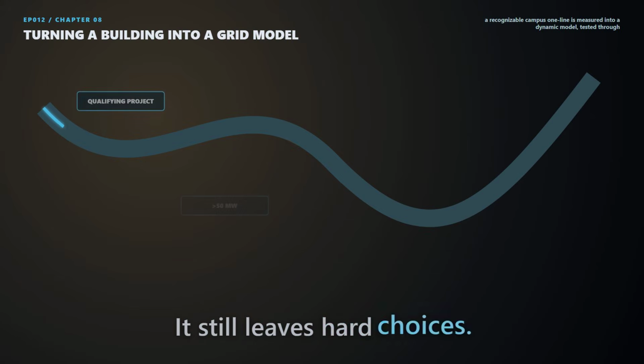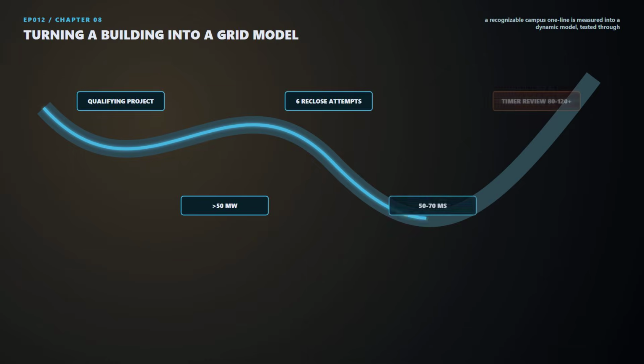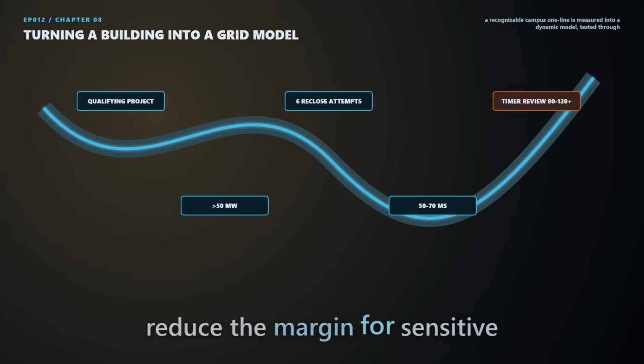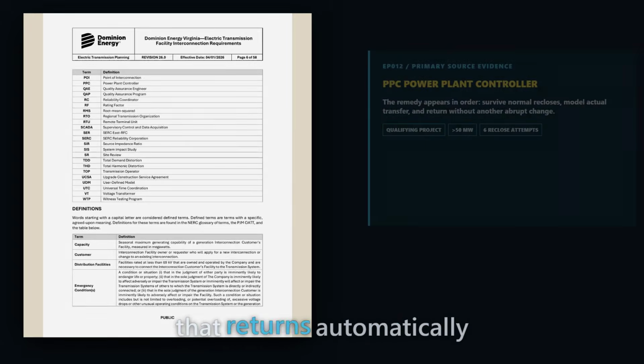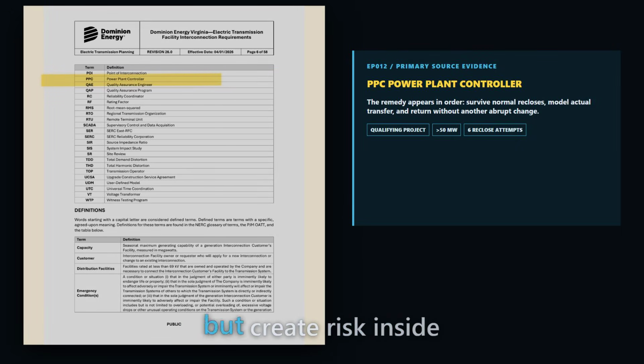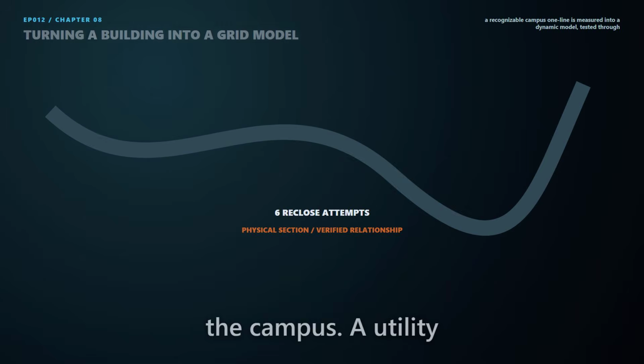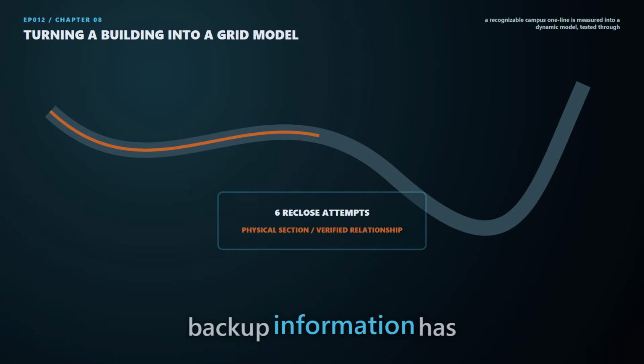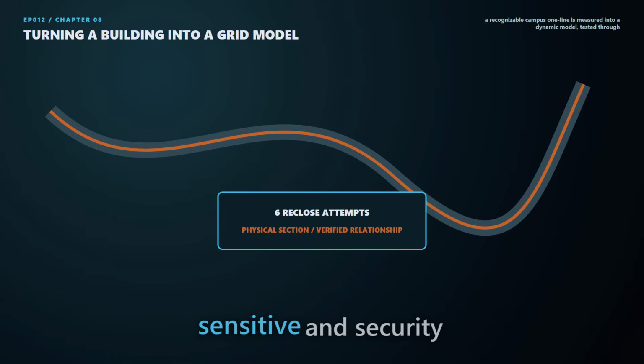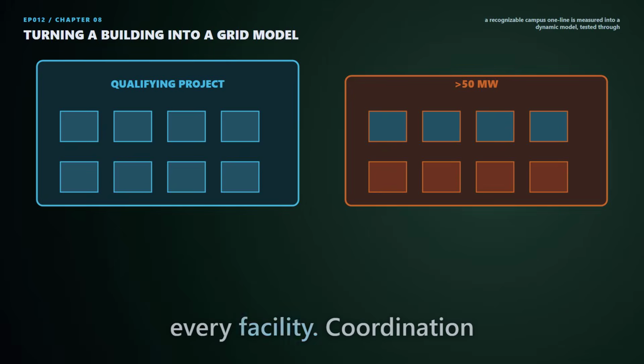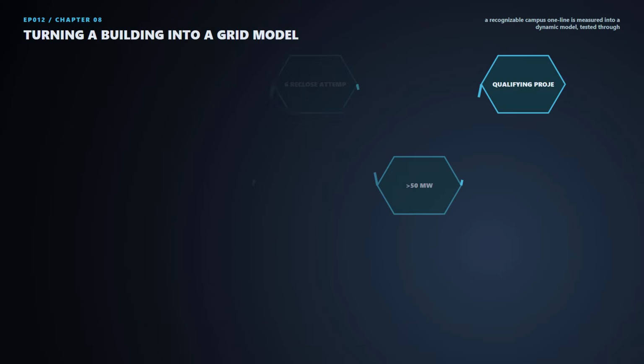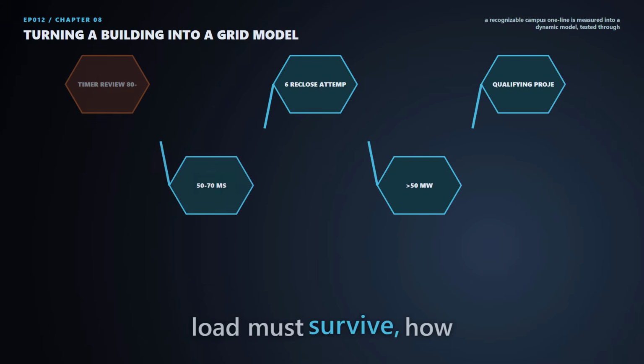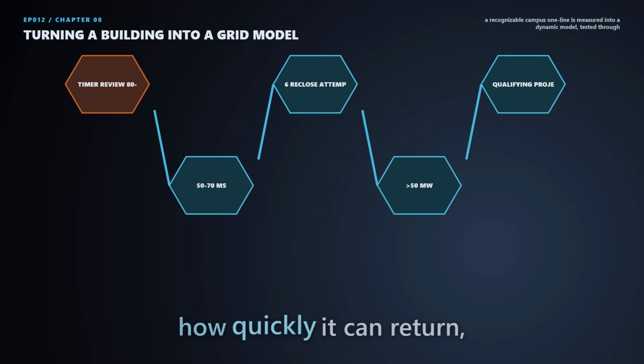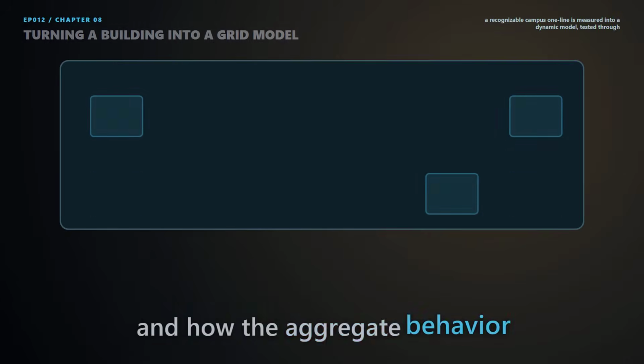It still leaves hard choices. A timer that waits longer may improve ride-through but reduce the margin for sensitive equipment. A controller that returns automatically may help the grid recover but create risk inside the campus. A utility that requests detailed backup information has to protect commercially sensitive and security-relevant data. There is no single setting that fits every facility. Coordination means agreeing on performance at the boundary, what the load must survive, how it communicates a transfer, how quickly it can return, and how the aggregate behavior will be tested.